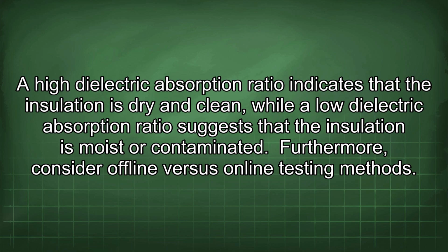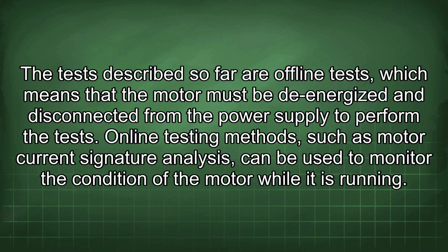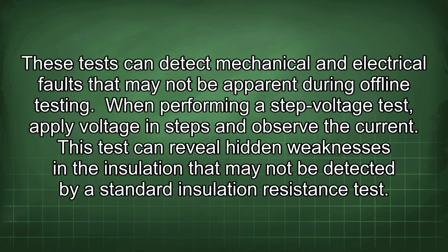Furthermore, consider offline versus online testing methods. The tests described so far are offline tests, which means that the motor must be de-energized and disconnected from the power supply to perform the tests. Online testing methods, such as motor current signature analysis, can be used to monitor the condition of the motor while it is running. These tests can detect mechanical and electrical faults that may not be apparent during offline testing.